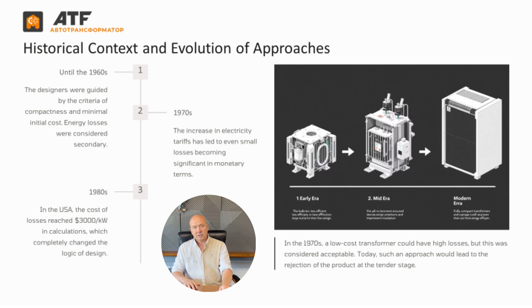Another example. In the 1970s, a cheap transformer with high losses might have been acceptable. Today, such a product would be rejected at the tender stage due to excessive long-term costs. So what is loss capitalization in practical terms? Transformer losses fall into two categories. No load losses. These are constant and occur even when the transformer is idle. Load losses. These depend on the current during operation.